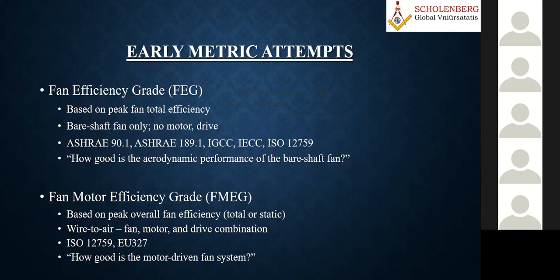That's what you have to consider for the fan efficiency grade, depending upon that. Now, talking about this, what is a bare shaft fan and peak fan efficiency, because when selecting the fan, whether it's a blower or fan—fan is a general term used everywhere—the fan efficiency grade depends on this. We also have fan motor efficiency grade, FMEG.